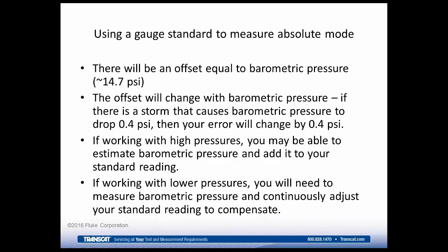So now you know that the actual pressure is 1,014.7. That will allow you to continuously adjust and take into account the changes in barometric pressure when you're trying to calibrate an absolute mode device using a gauge standard.